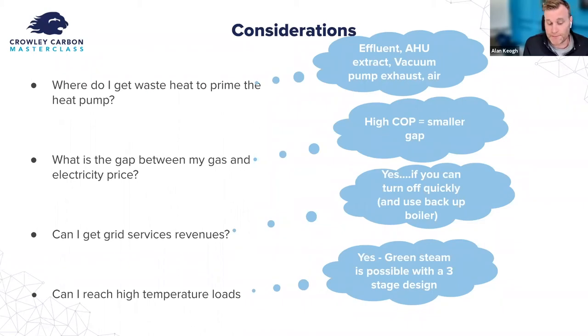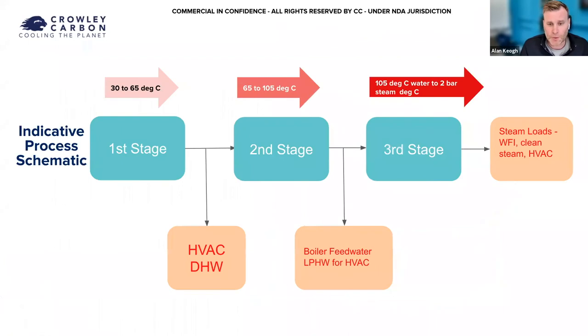And finally, can I use the heat pump to generate high temperature thermal requirements, so steam effectively? This is a configuration we're working on with a number of customers. We haven't put in all the detail because some of it is IP protected, but it's a three-stage heat pump, and each stage is a different technology and a different refrigeration gas. The first stage lifts the heat from circa 30 to 65 degrees.